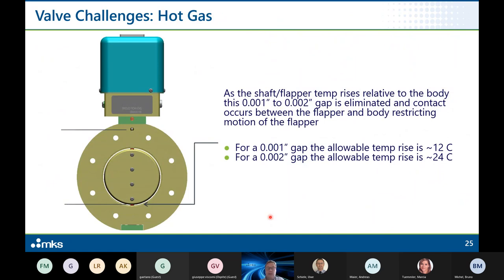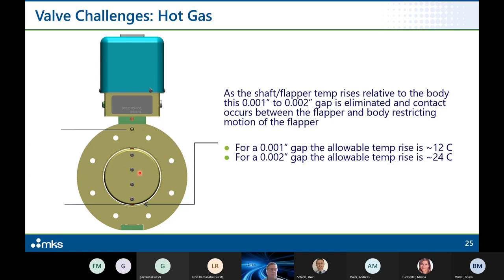Another challenge is heat: the process generates heat that warms the flapper, and chamber cleaning steps to remove deposition can cause reactions on the flapper surface that also generate heat. As the flapper temperature rises it expands, reducing the gap between the body and flapper. You can select different gap sizes to optimize for your process temperatures and operating conditions. That concludes today's talk.